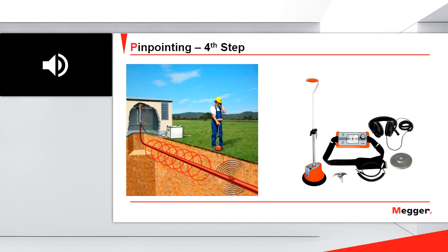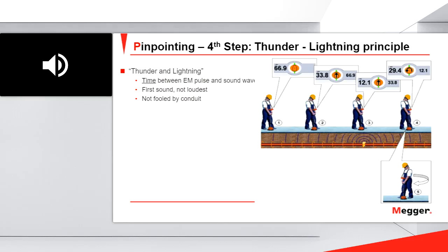So in this fourth step, the pinpointing, I will use a pinpointer. In the case of Megger, the pinpointer that we use is the Digiphone. It's a very nice tool. For instance, what we are seeing in this picture is a person trying to pinpoint the fault. And we see here this number, 66.9 milliseconds. That means the electromagnetic signal arrives, and 66.9 milliseconds later, the acoustic one arrives. So this is the difference between the arrival of both signals.